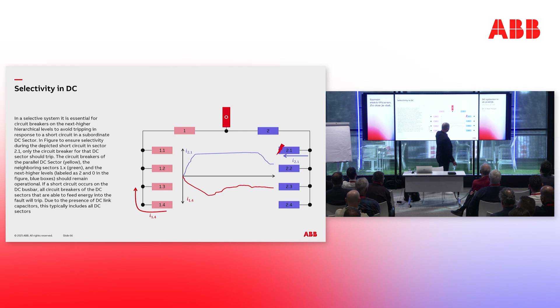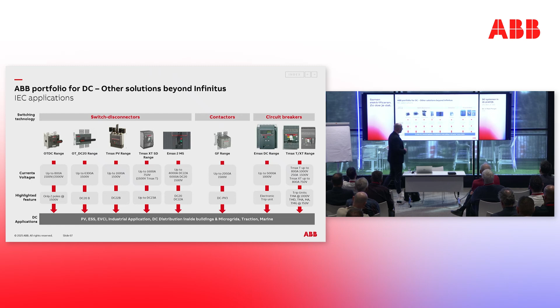But where you have, or can have, selectivity is between the sectors. If there is a fault in this sector, the solid-state circuit breaker connecting the two large sectors will interrupt and make sure that this part of the system remains operational. That is why, for DC protection, the rest of the devices we have still remain important.